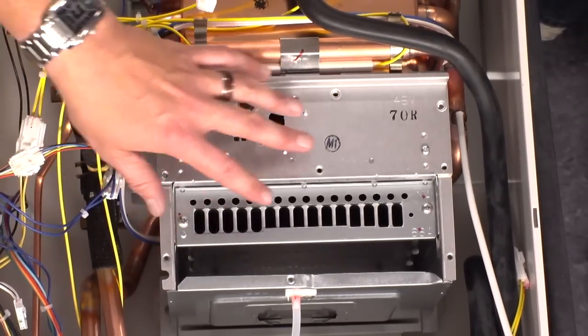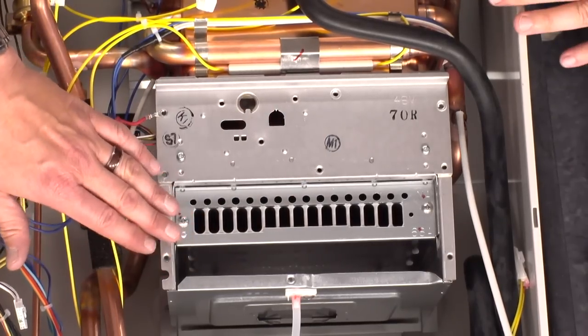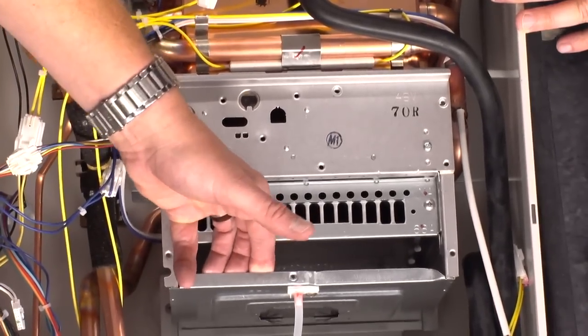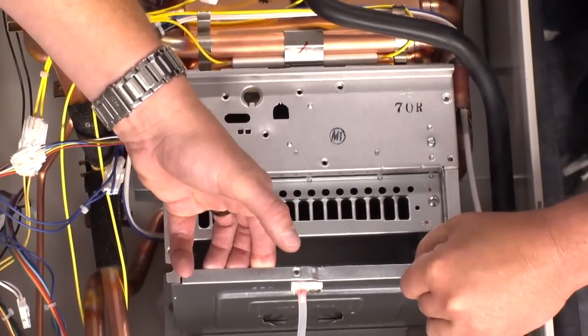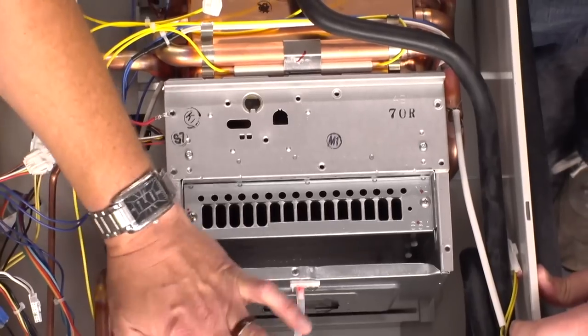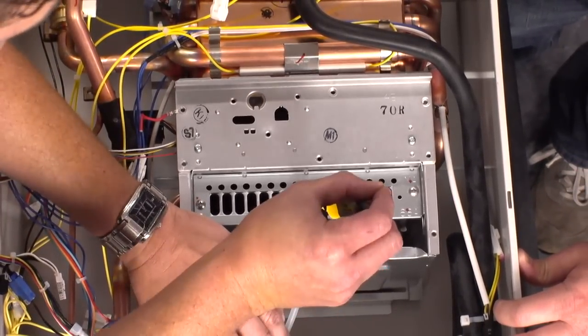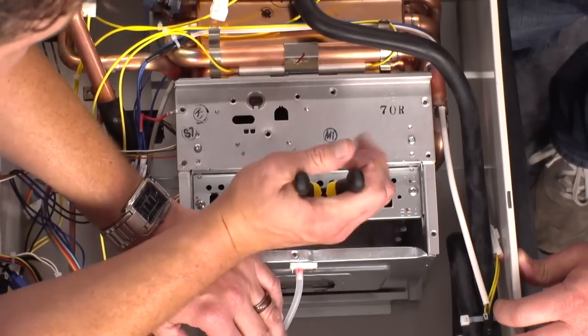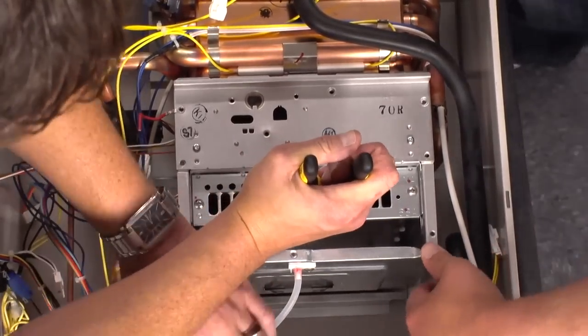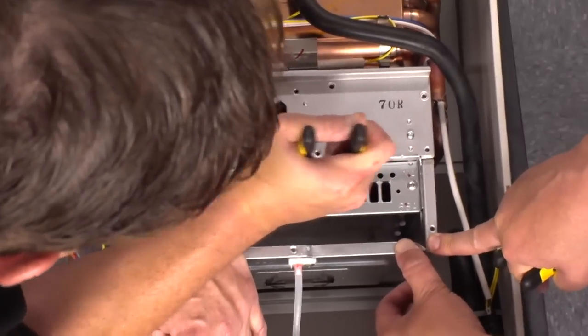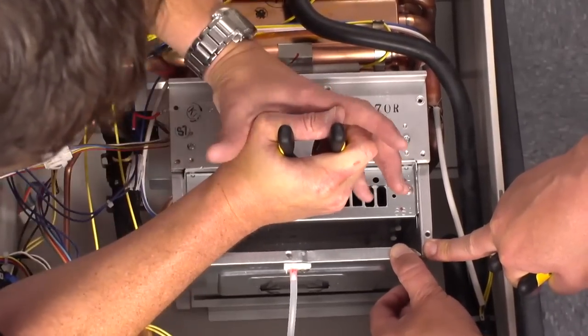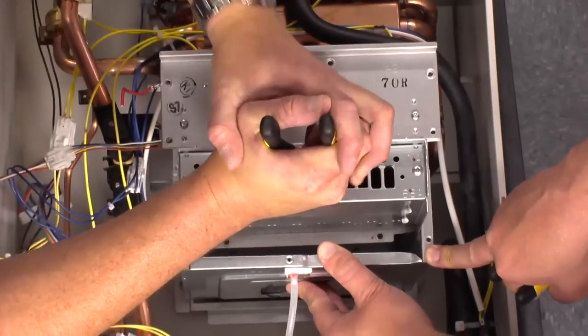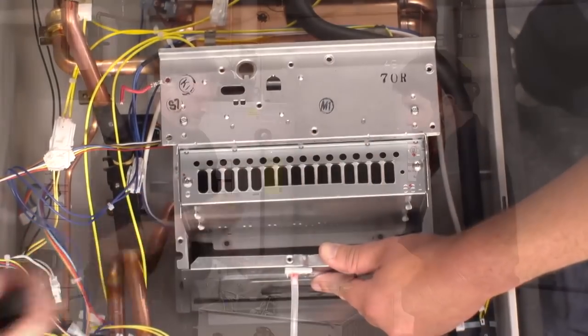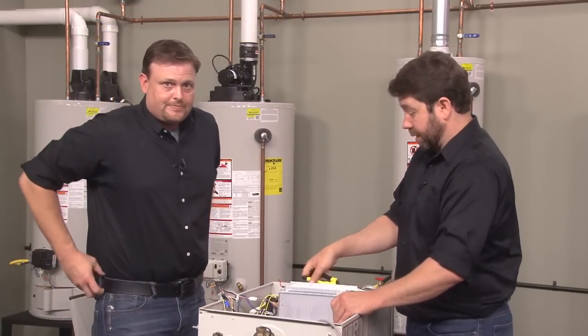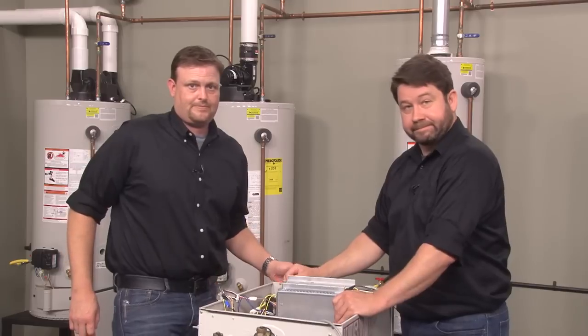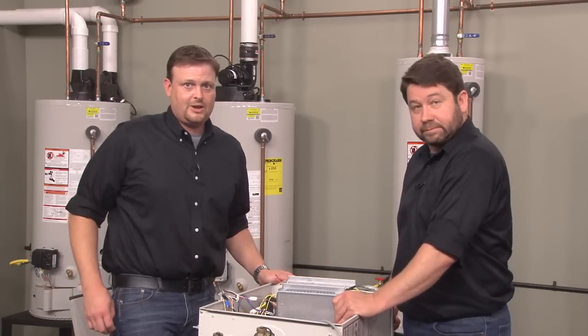All right, now here comes the fun part. We're going to pull out the burner. Now the thing about this is, if you lift up on this burner piece, the bottom piece of the burner, it comes up. So you're going to have to hold that down and take some pliers. Grab right there in the middle. Now it's got some sharp edges, so be careful that you don't cut yourself. And a little gentle pressure or a quick yank will break that free and let it pull on up. There you go. Good job.